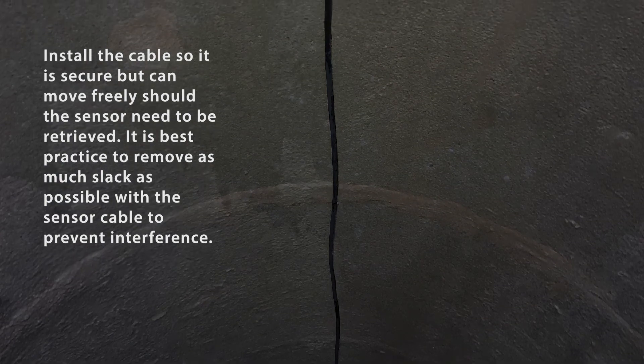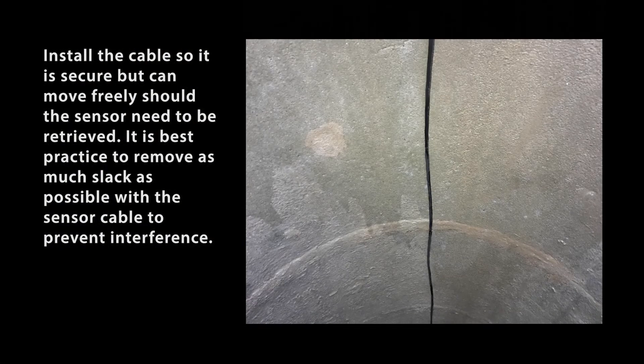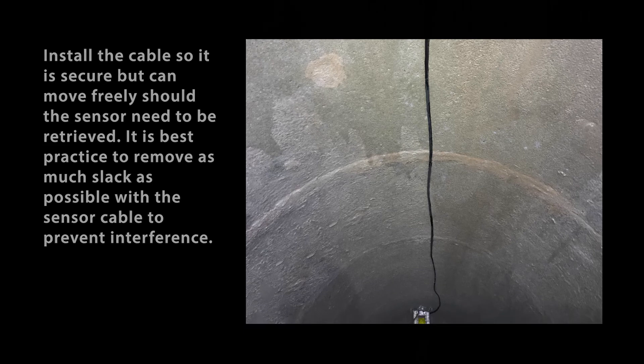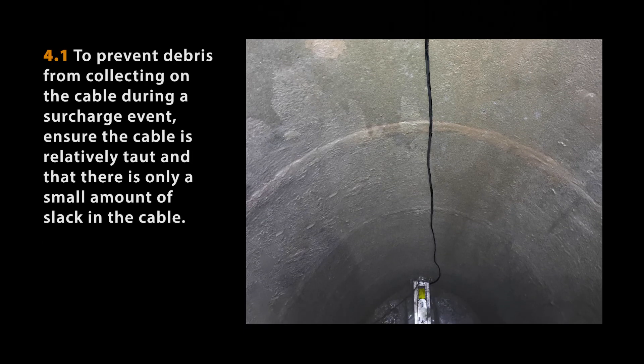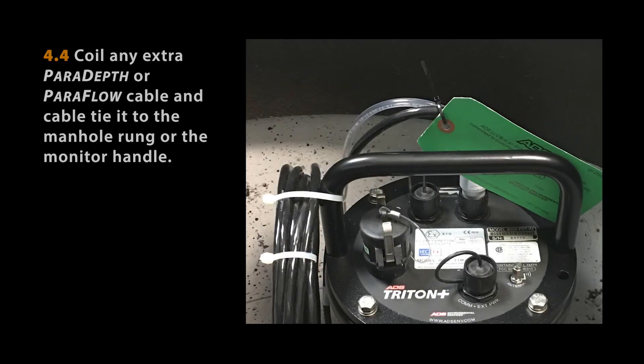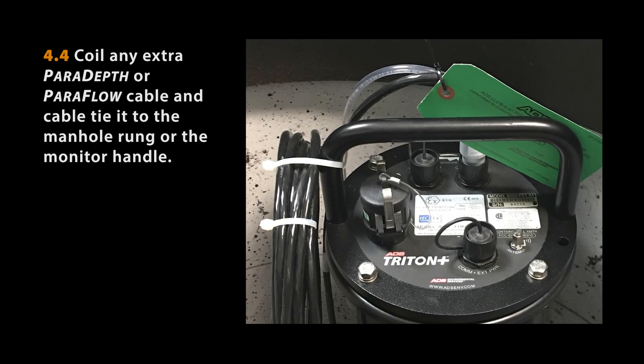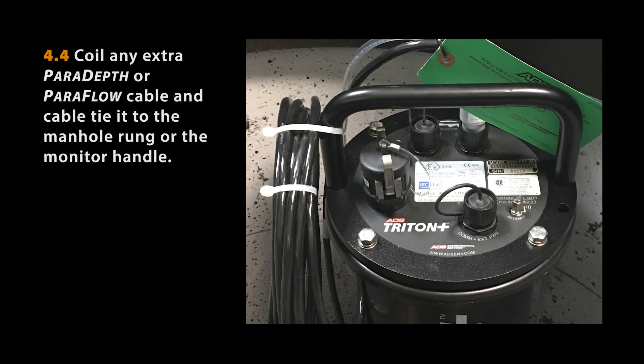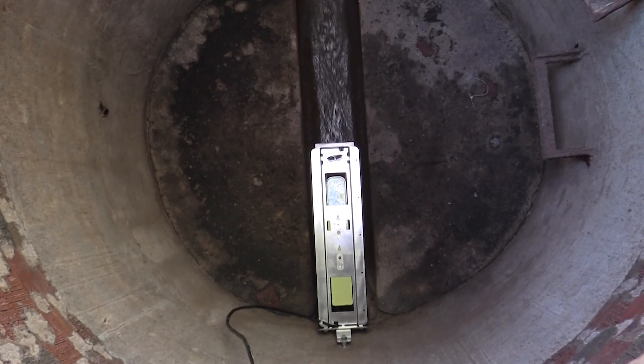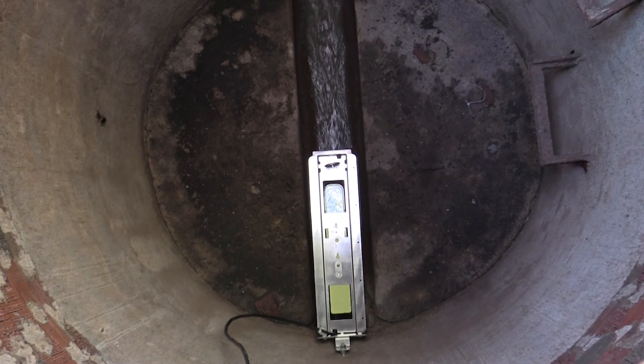The installation is almost complete. The last step is to secure the sensor cable. Let the sensor hang, ensuring the cable is relatively taut to reduce the potential for debris buildup during a surcharge event. Coil any extra sensor cable and cable tie it to a manhole rung or the monitor handle. The topside retrieval system installation is now complete.